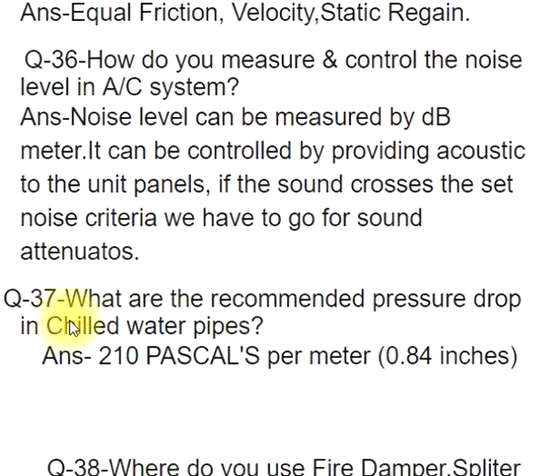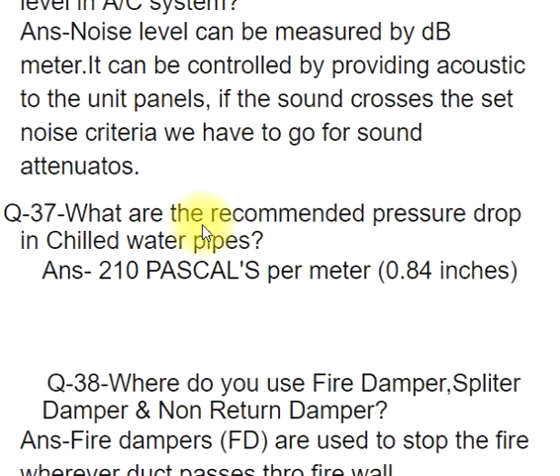Q37: What are the recommended pressure drops in chilled water pipes? ANS: 210 pascals per meter, 0.84 inches.